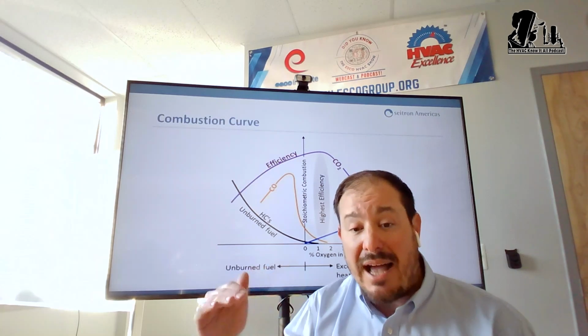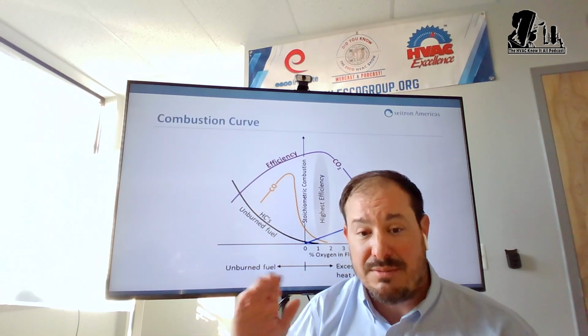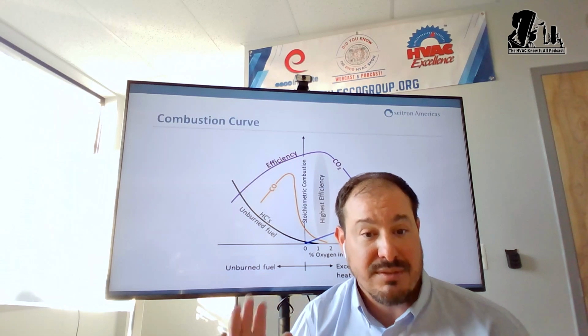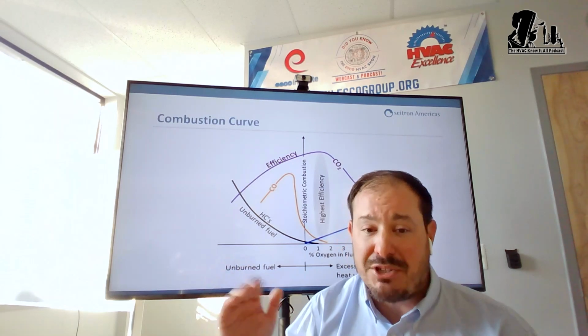Now, what high efficiency condensing equipment does is, because they run at lower temperatures, typically in the exhaust, there's much, much less of it. The higher the temperature you go, the more NOx you create. That's how that works. So that's why it becomes a bigger issue on bigger commercial and industrial boilers, because you're running 300, 400, 500, 600 degrees Fahrenheit in the exhaust or in the stack. So that's kind of the difference.